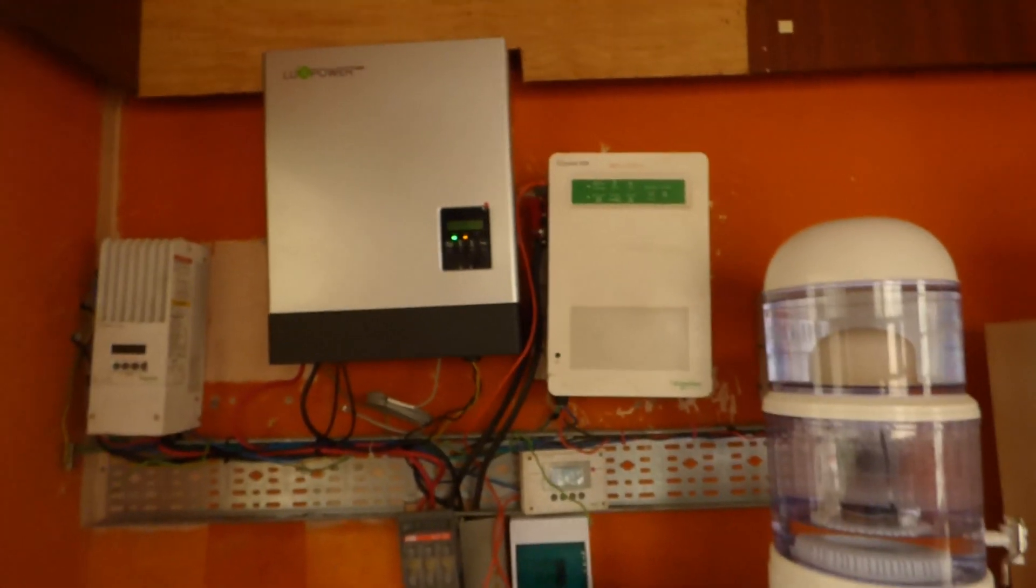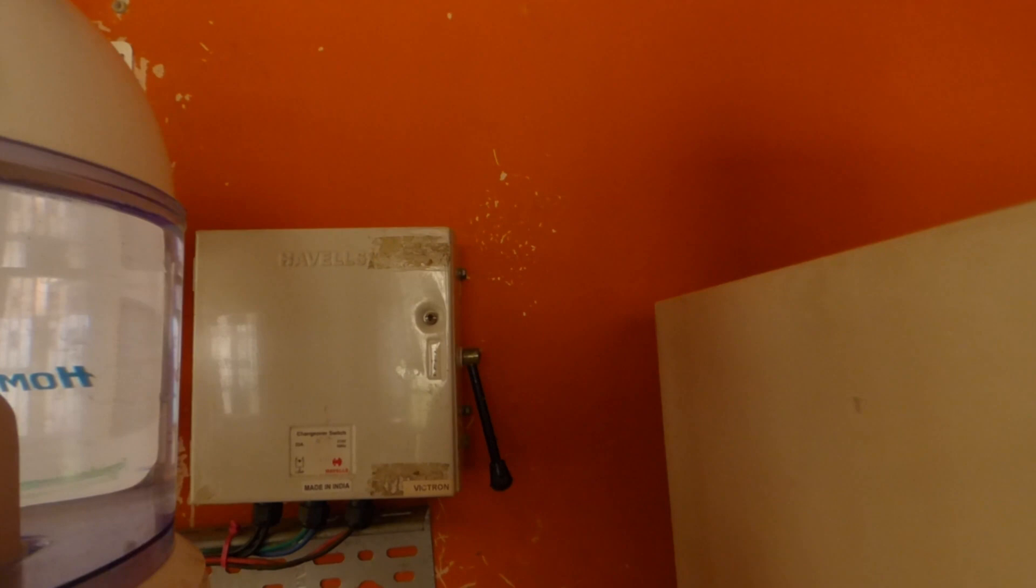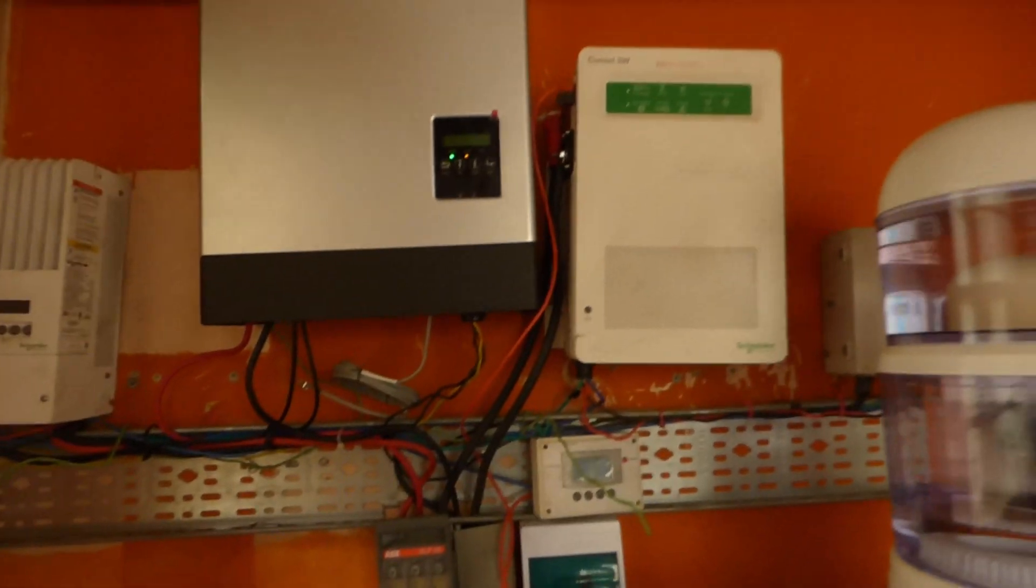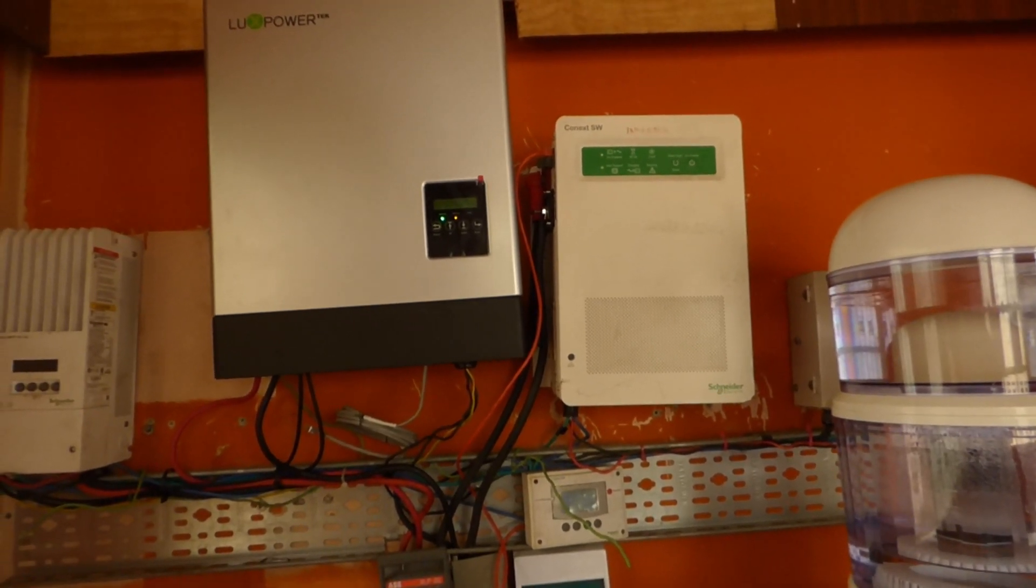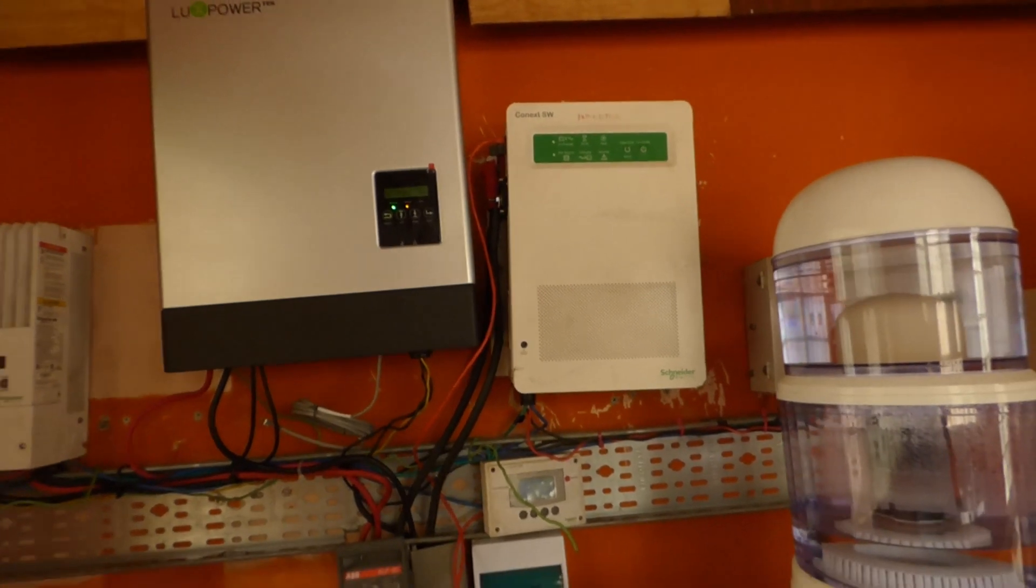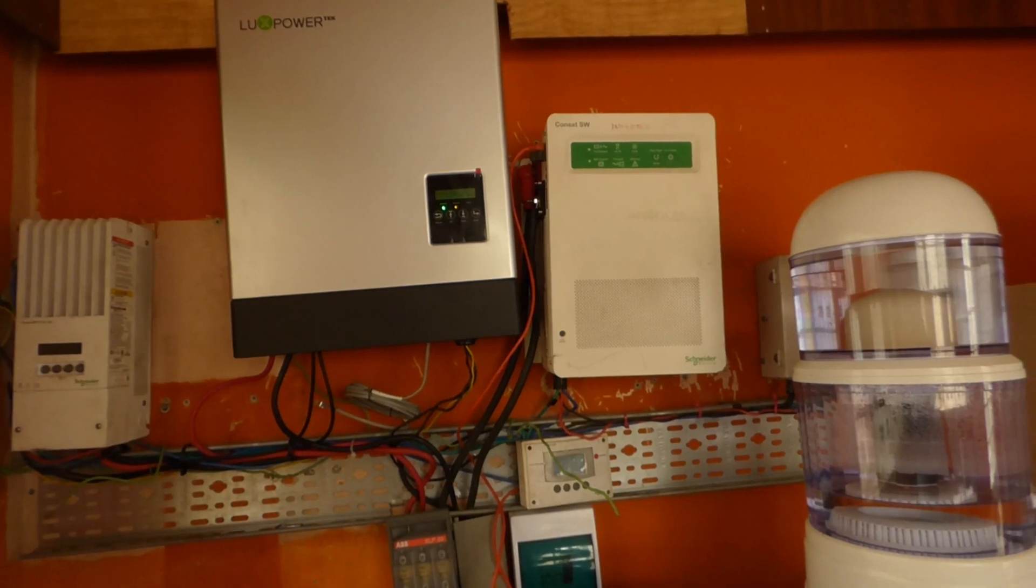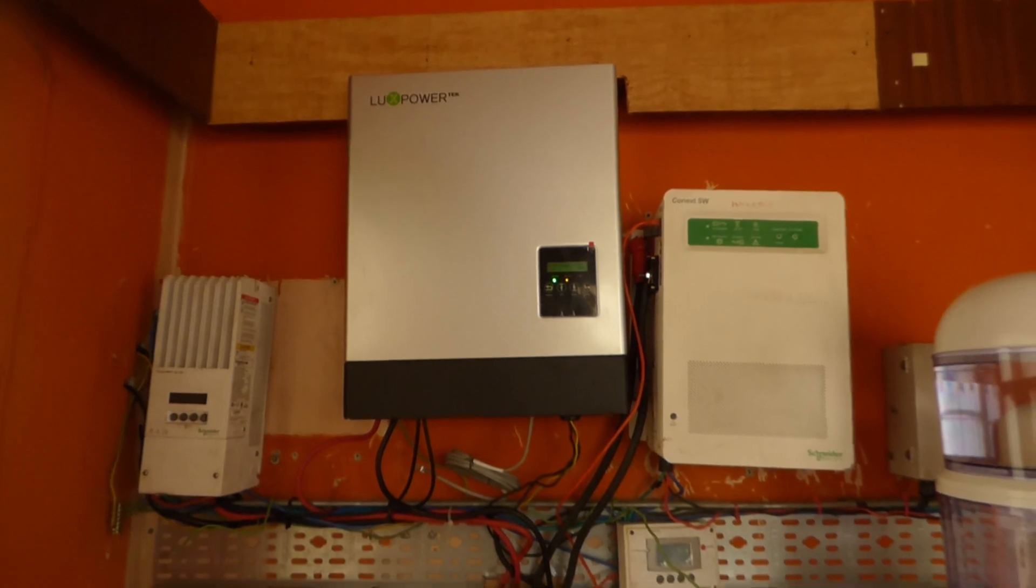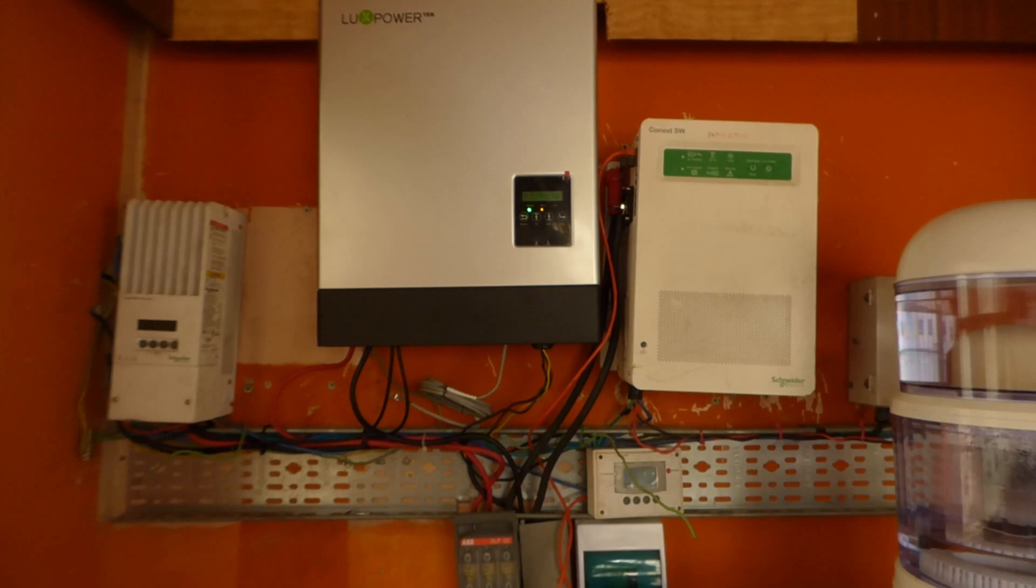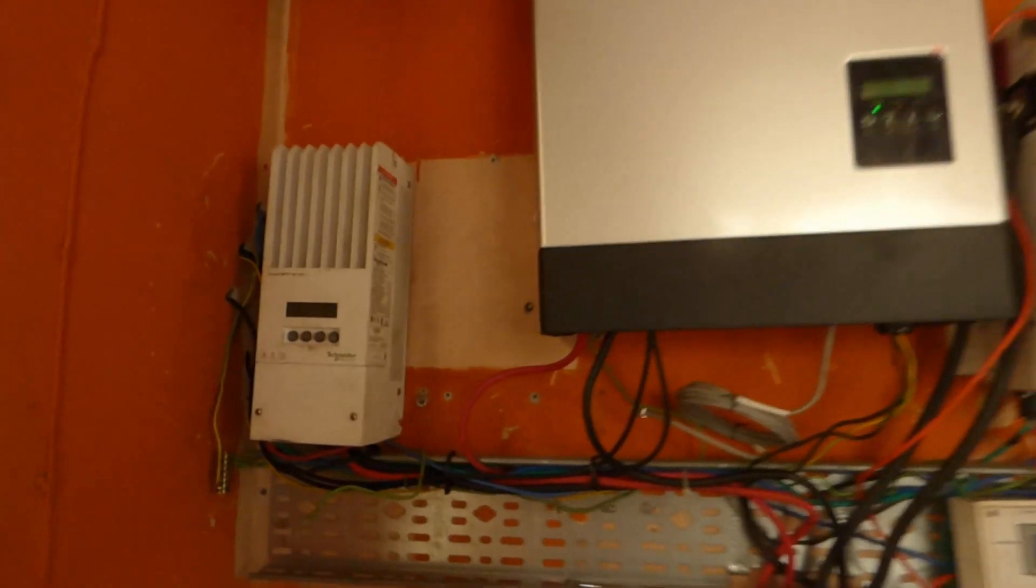So I thought they were referring to doing a chassis bond earth, and I said I had not done that yet. They said well in addition to doing that I also have to have the EPS earth cable. So this morning I turned it off, actually I bypassed it, so I'll change that setting for you - no longer be Victron, it will go back to say Luxpower, and then on top will be the Schneider Conext. So I bypassed it and I ran the Conext all through the night so that our appliances will stop shocking people. This morning I got an earth rod - I'll show it to you in a second.